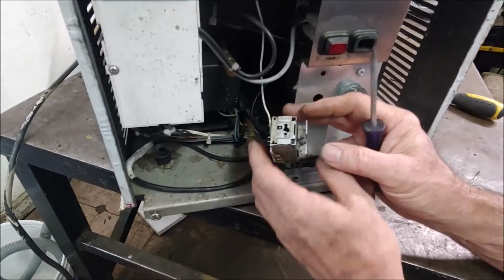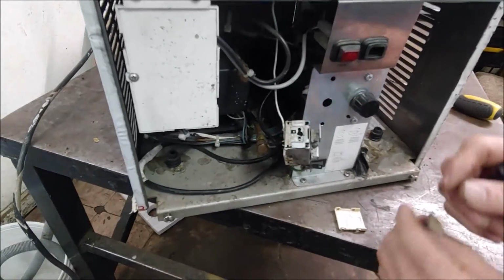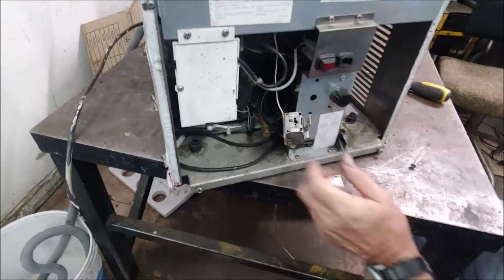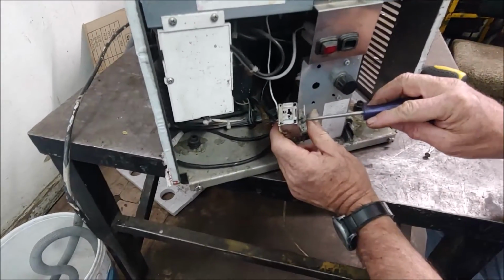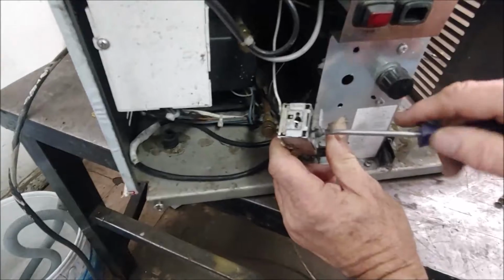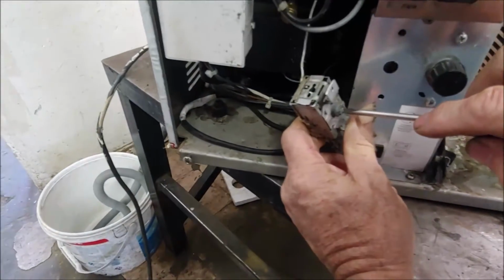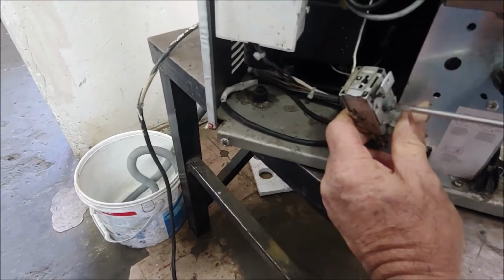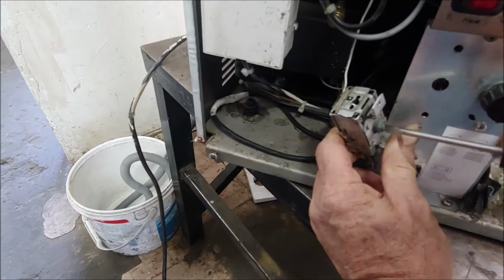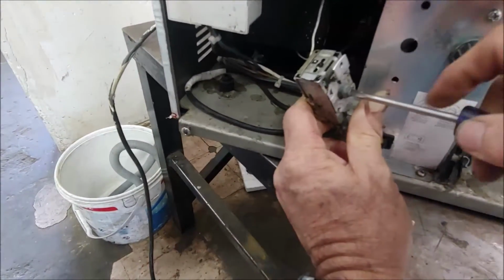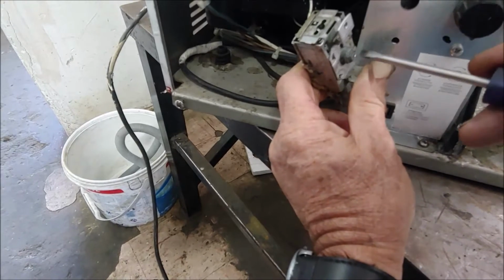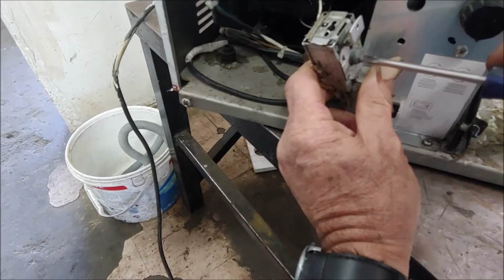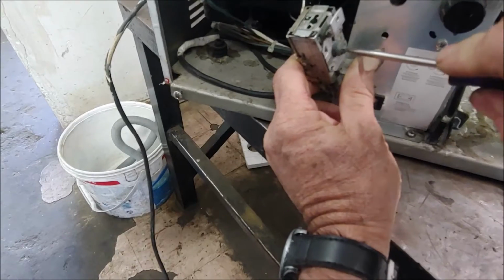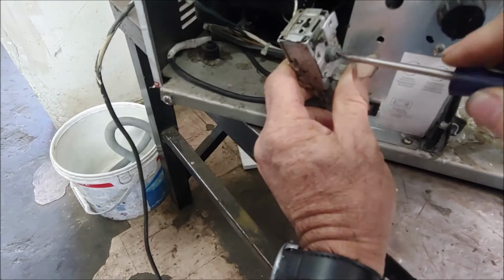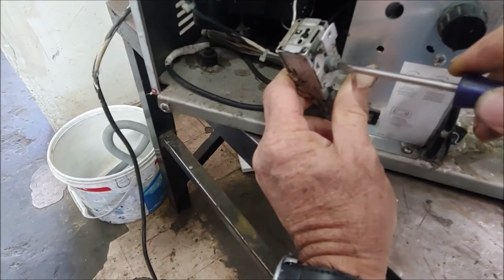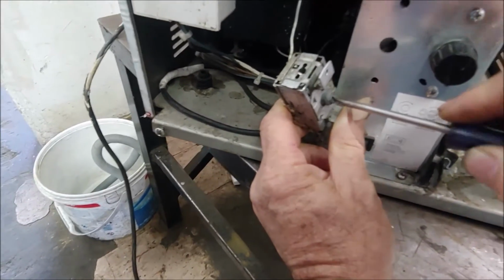So the calibration inside this thermostat is wrong. It happens - it's a spring against the diaphragm, and it loses some elasticity over the years. So how I fix it: I turn this thermostat to more or less the middle of its range. If you have a look, this knob can rotate just about 360 degrees. So we go to the middle, which is about there, and at that point you'd like the thermostat to switch off. You can hear a little clicking sound it makes on and off, and you'd like that clicking sound in the middle of the range.